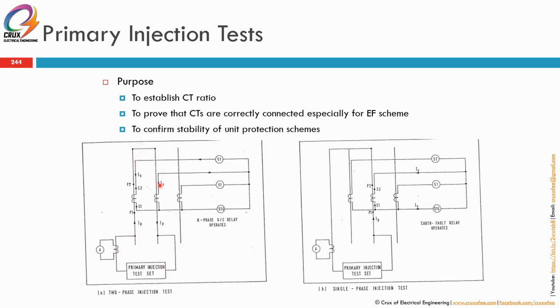So in this case, let's see. This can indirectly also test the earth fault. Okay. So number one, you can test for the overcurrent. When you are injecting here, the I primary is going through here, through the red phase and returning through the yellow phase to the test set.